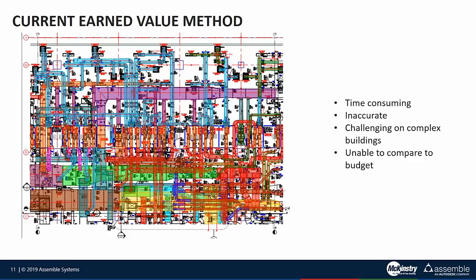There's also a ton of up and down movement throughout the floor when you have layers and layers of overlapping ductwork. It's also tricky because, as you can see in the picture, there's those layers, so you're trying to guess and remember exactly which piece is installed and trace it as the lines go away under some other duct. The other biggest problem is we're unable to compare it to the budget.